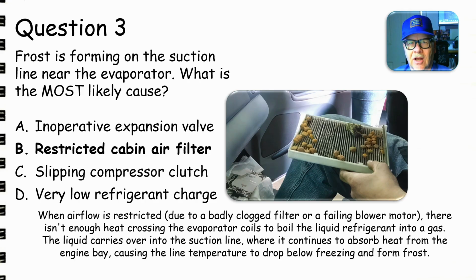So frost alone is not a reason to go looking for a problem. If the air conditioner's cooling real good with frost on the suction line, unless... I guess you could use that for upsell, but upsell is something I don't typically enjoy. Customers pick up on that when you try to upsell them, and then they go to another place and get told they don't need that stuff. That happens every day.